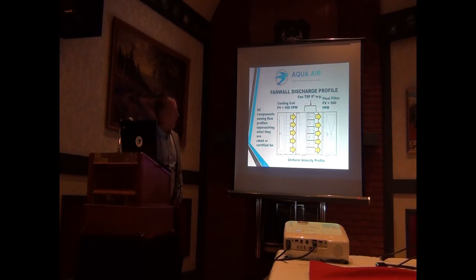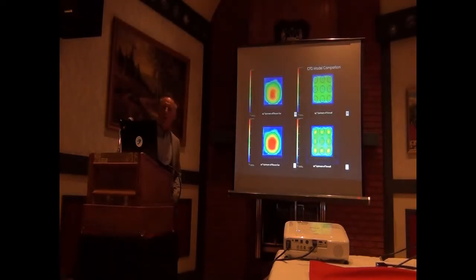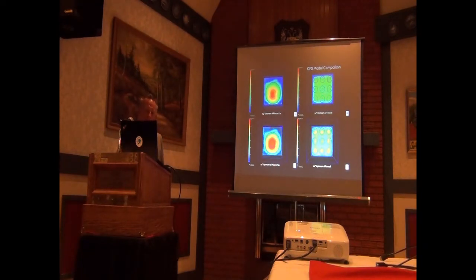Like the plenum fan, we're only showing the one opening here, but again, you could have multiple openings on the other end of this unit if you require them. In general, because the fan wall uses smaller fans and motors, you're going to have an even smaller footprint than most design units. Talking about that, a good way to envision how that wall of air is moving towards you in a unified manner.